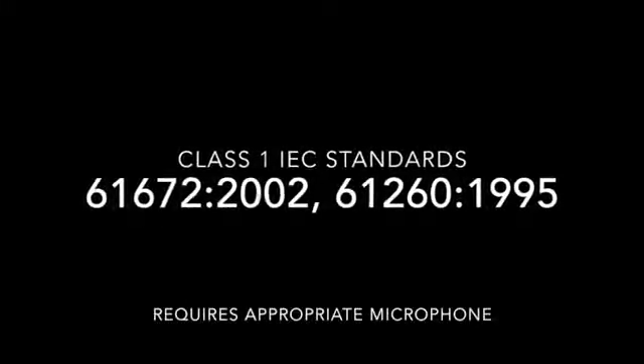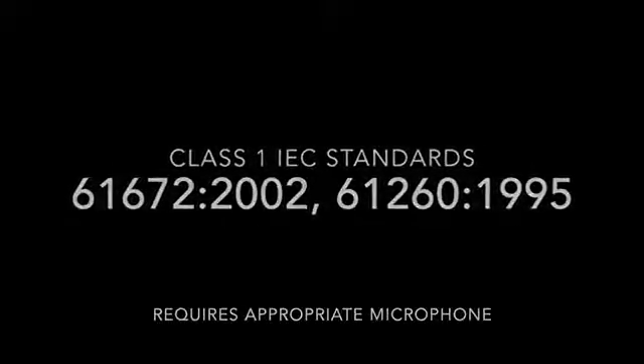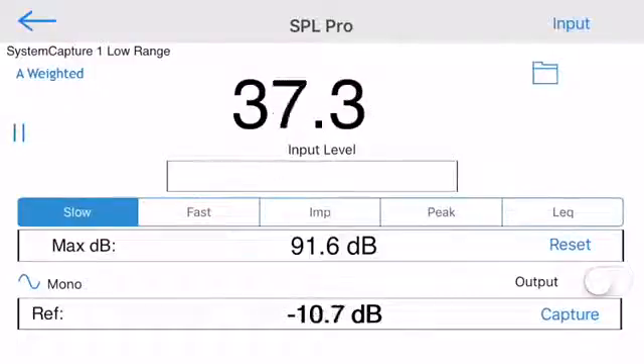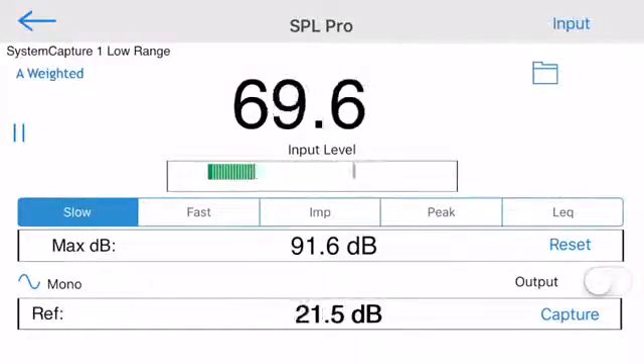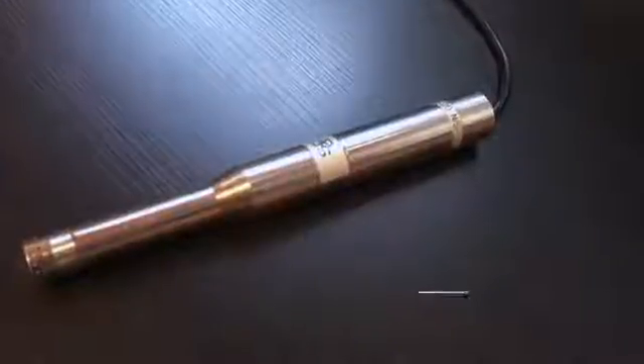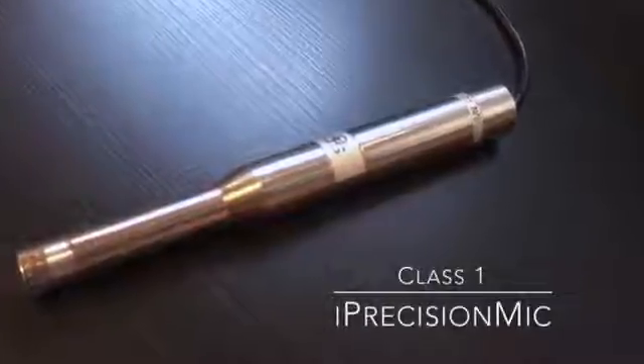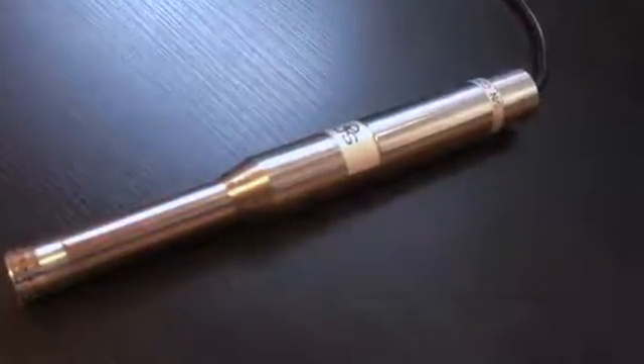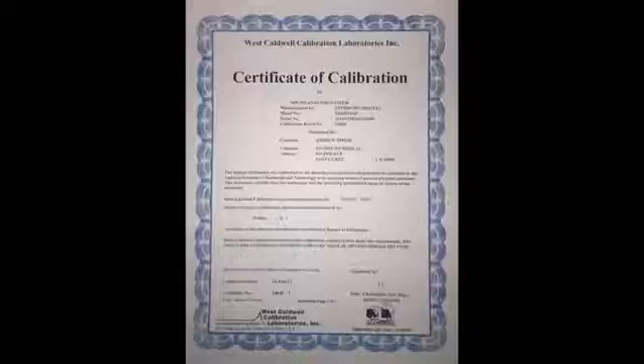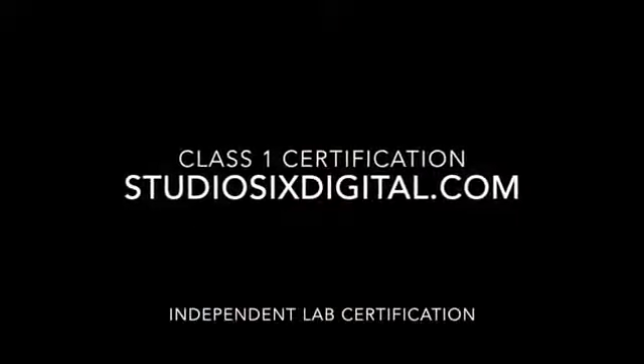app. The algorithms and filters in SPL Pro Sound Level Meter are designed to meet all industry standards for a Class 1 instrument. SPL Pro works with the internal iOS device microphone as well as external microphones, such as our iTest mic for Class 2 performance and iPrecision mic for Class 1 system performance. Using iPrecision mic, it is possible to have the system certified as Class 1 by an independent test lab. See our website for more information about this.